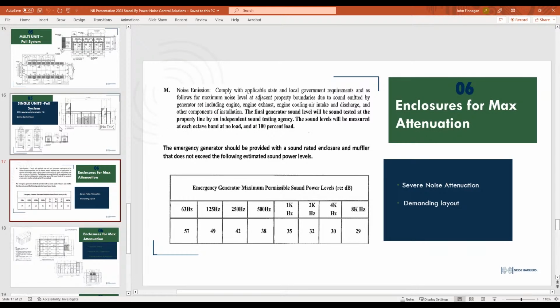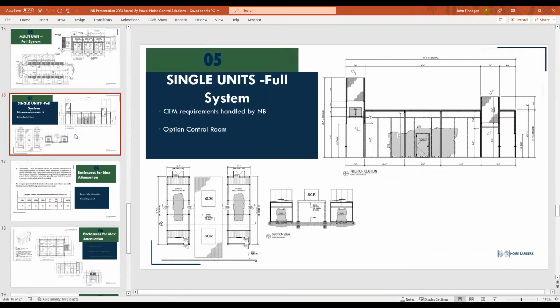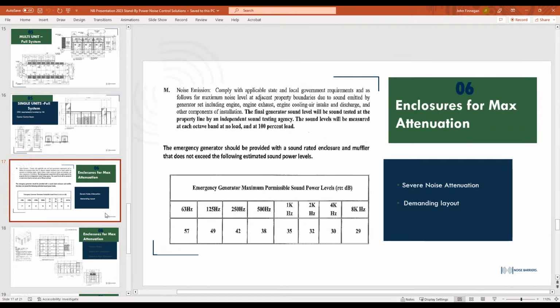I'm just going to jump off from the full systems, and now trying to keep this to a half hour. This is the max - this is when the genset manufacturer is not going to even pretend that he can provide an enclosure for it, because they do love selling enclosures. I have nothing against them. But this is where you get to attenuation levels of needing 45 dBA anytime this thing is running 3 feet away.